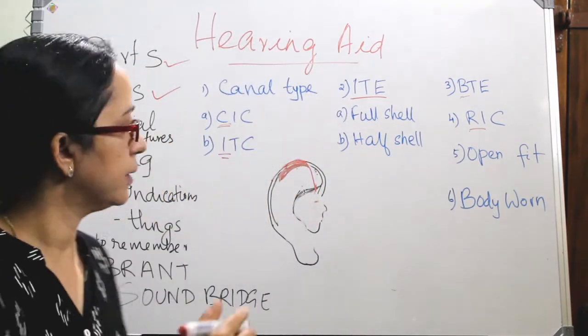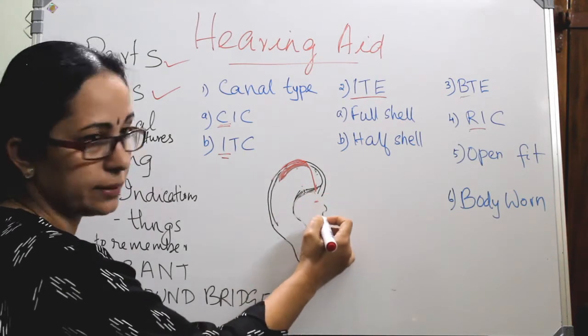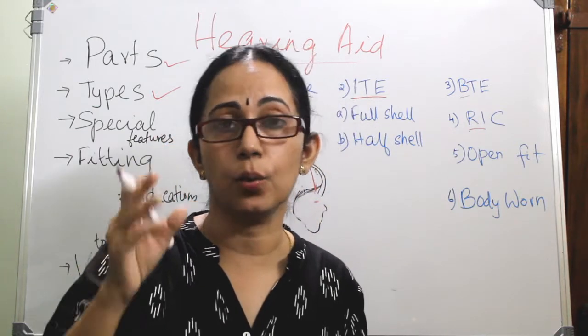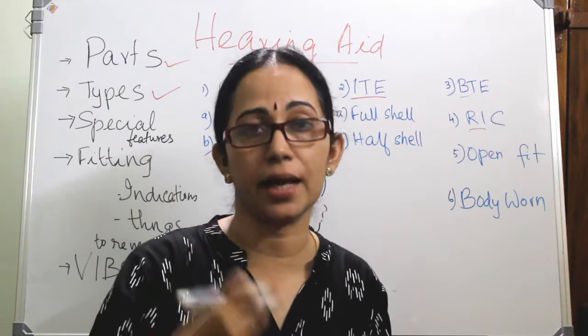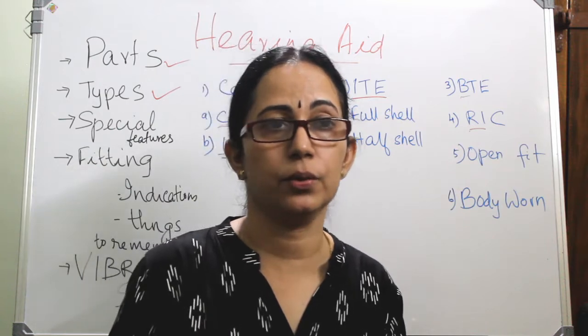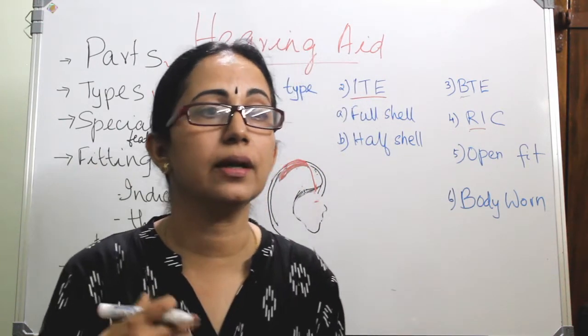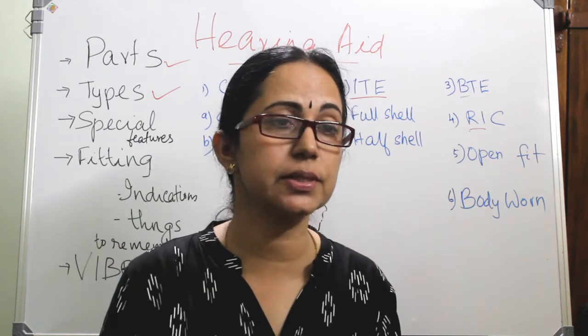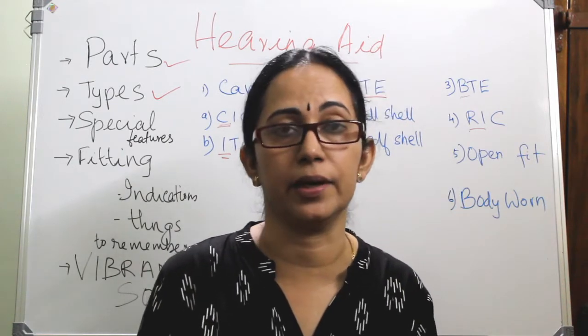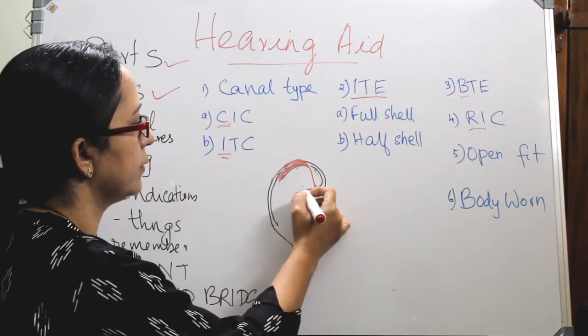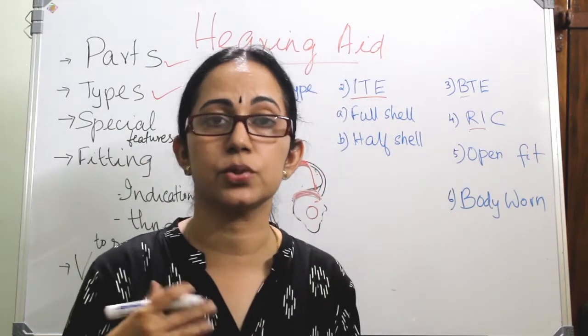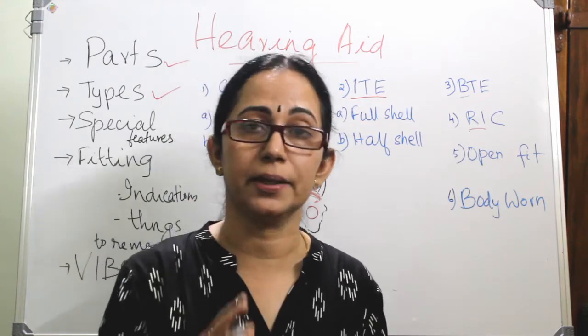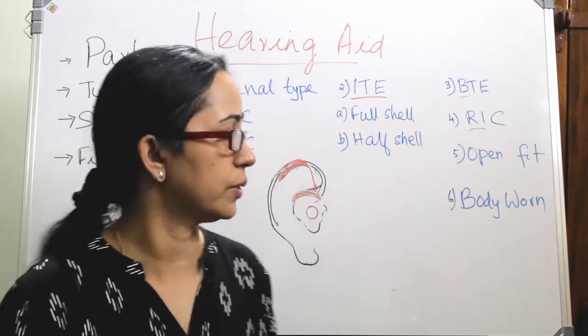Open fit is a variation of BTE where the external auditory canal is kept open. This means low frequency sound reaches the ear naturally, and amplification occurs only for high frequency sounds. The main advantage is that the patient's own voice sounds better and more natural. However, because it uses a non-custom-made component, visibility is more and it is cosmetically less appealing.